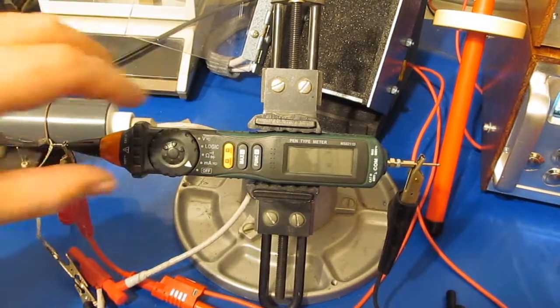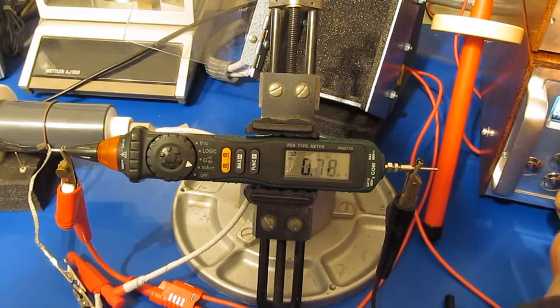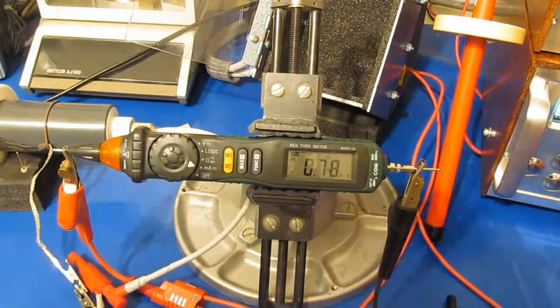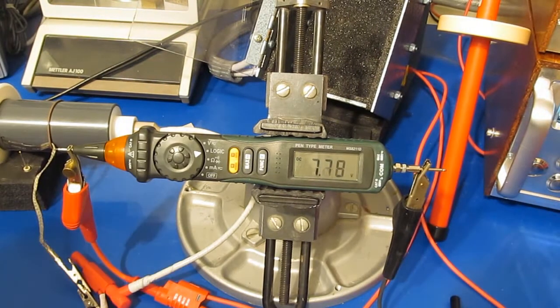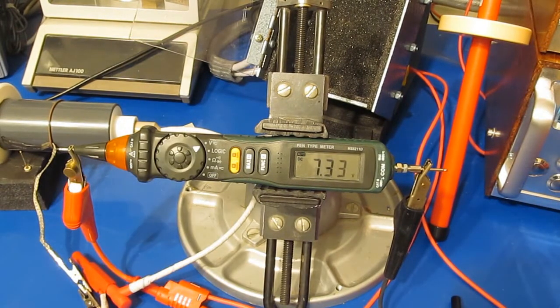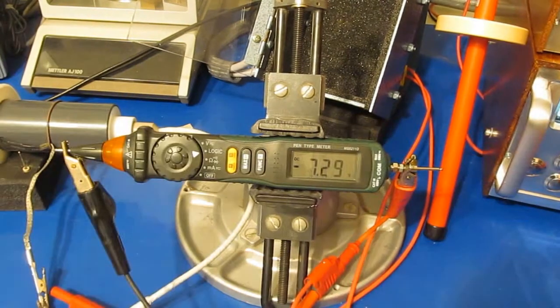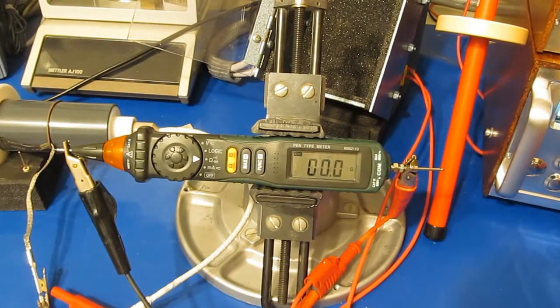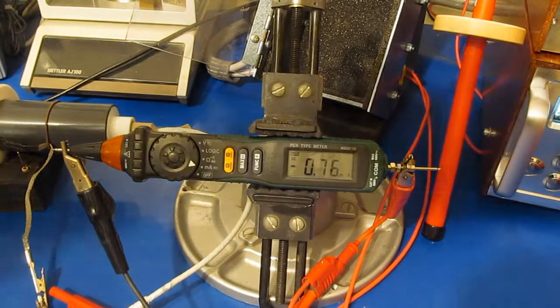Then we'll go ahead and reverse the two leads. Again this will be 5 transients in each mode. 1000 volts, 2 ohm source impedance, 100 microsecond full width half height. Alright that's it.